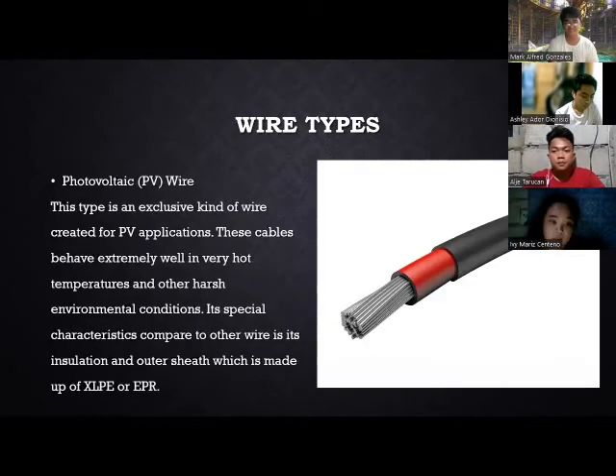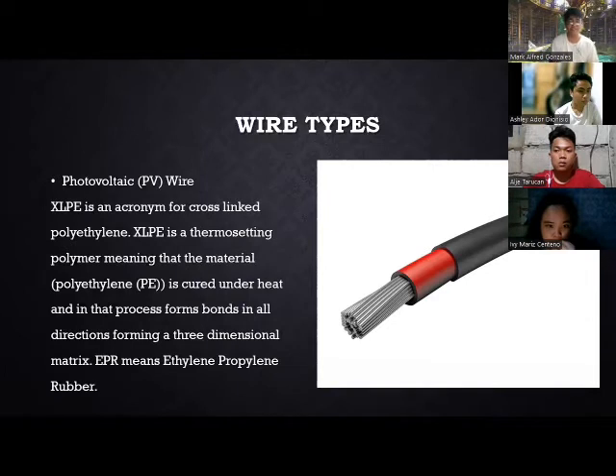Okay, next naman ay yung photovoltaic wires. This type is an exclusive type of wire created for photovoltaic applications. These cables behave extremely well in very hot temperatures and other harsh environmental conditions. Its special characteristic compared to other wires is its outer sheath, which is made out of XLPE or EPR. Matibay siya. XLPE is an acronym for cross-linked polyethylene.